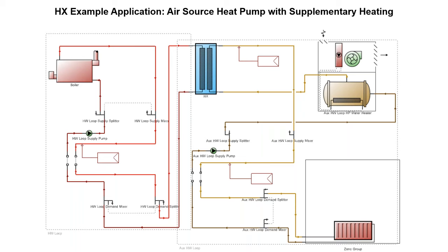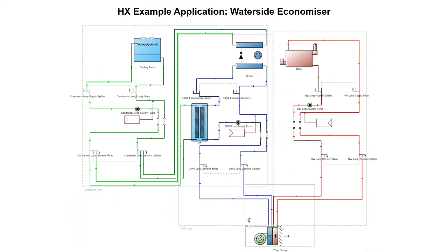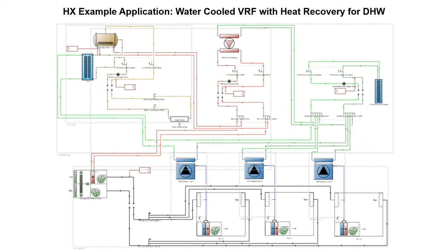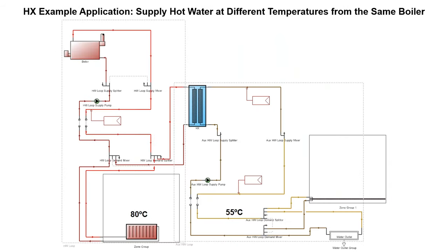Heat exchangers can also be treated as an EnergyPlus simulation artifact where in physical systems the loop connections might happen directly or via valves. When those connections are not directly connectable in EnergyPlus, a heat exchanger provides a way to connect those loops and transfer heat between them. Example applications include: an air source heat pump coupled with supplementary boiler heating; bypassing the chiller to use a condenser loop as a water-side economizer; water-cooled VRF with heat recovery for domestic hot water; and supplying hot water at different temperatures from the same boiler — which we will replicate.